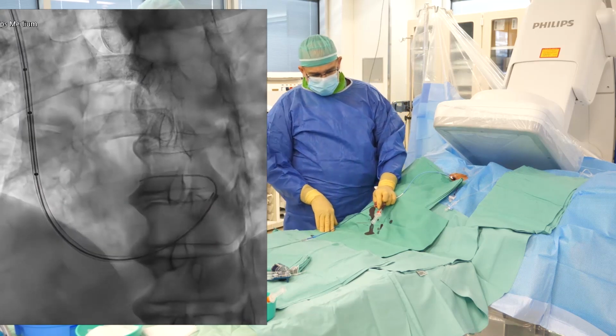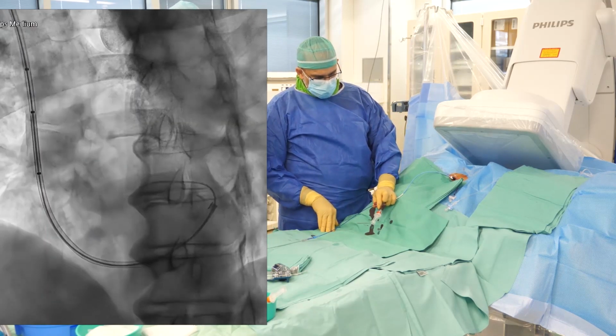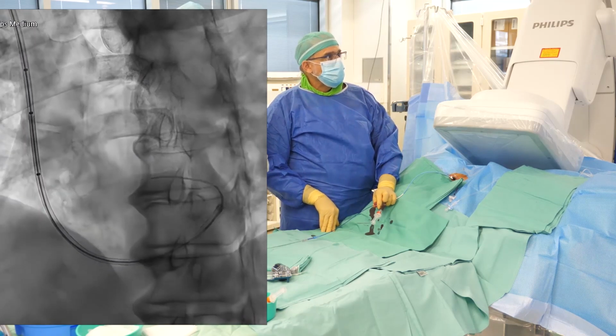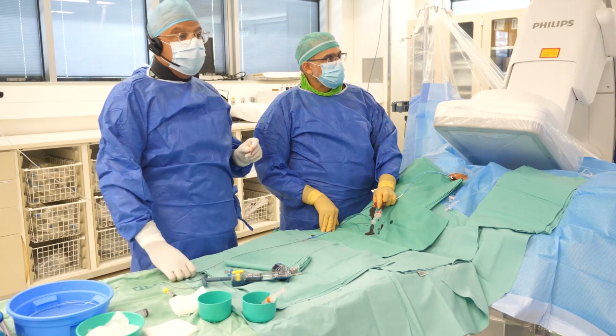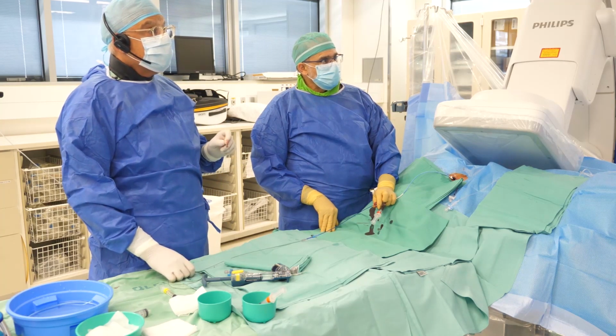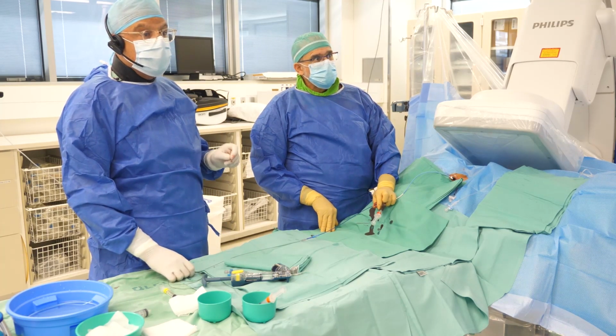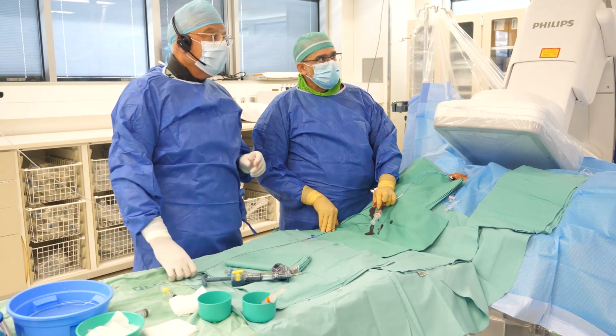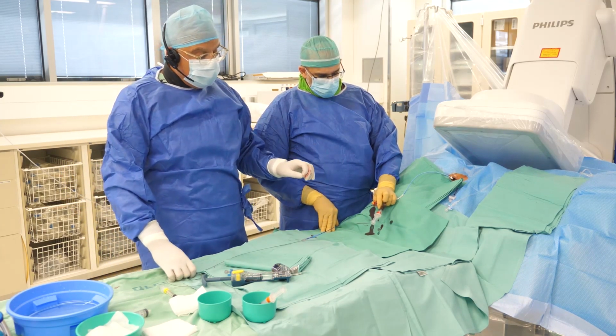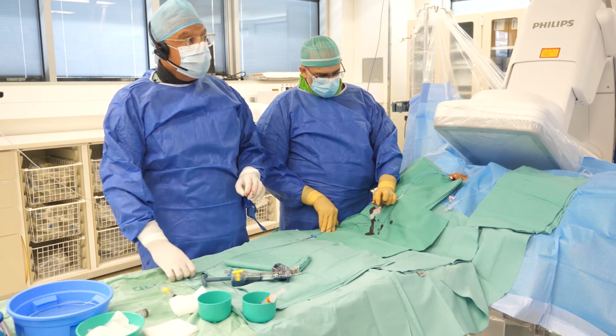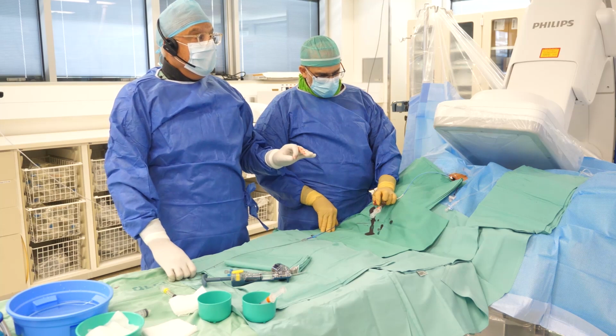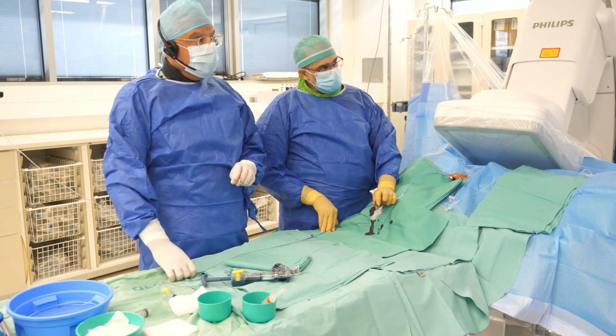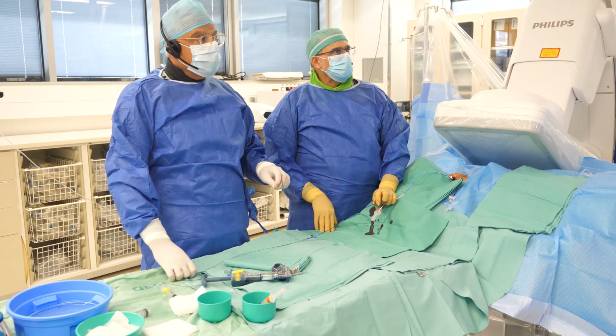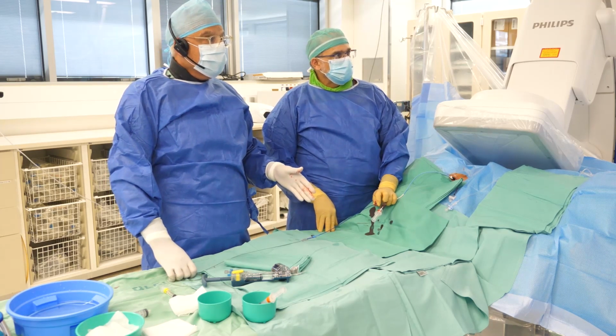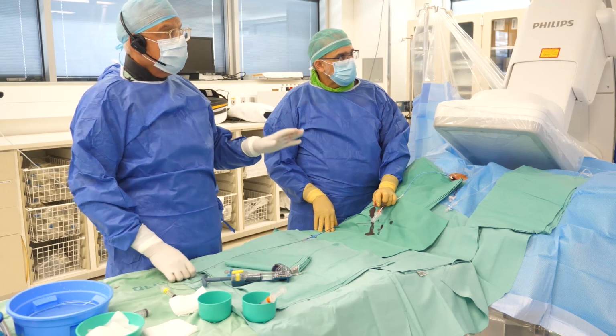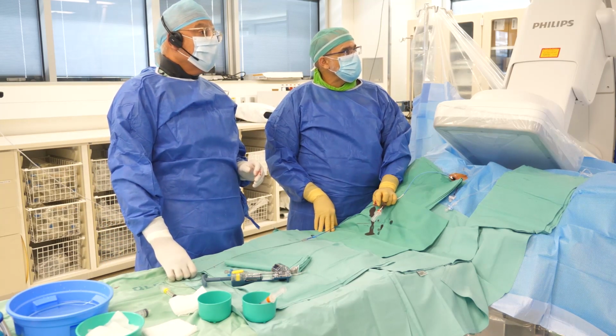Okay, we check to make sure that the reducer is well located between the distal and the middle marker, and it has not moved on the balloon, because if we have a suspicion that the reducer has moved on the balloon and it's not properly located between the markers, the only thing to do is to take out the guiding catheter and the reducer inside and leave the wire in place. Never try to take only the reducer outside and leave the guiding in. Take the guiding and the reducer out, start over again with a new reducer.